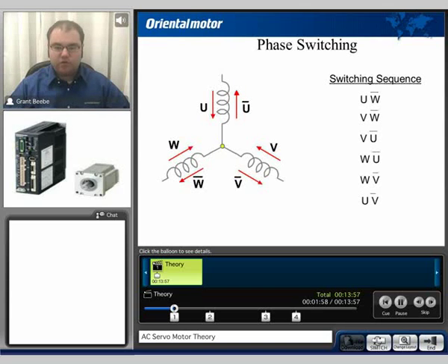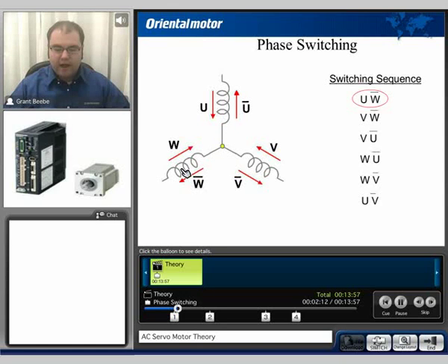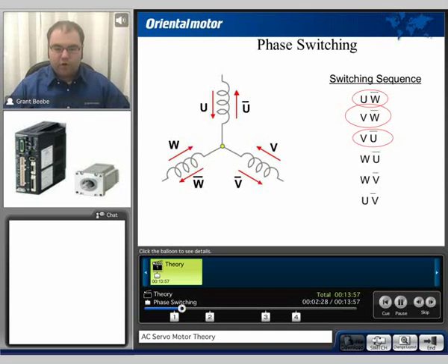The typical switching sequence will be shown here. On the first sequence, the U and the W are activated, so we have current running through U and then exiting out the W. On the next sequence, we have current running through V and then out the W. And on the third sequence, we have current entering through V and then exiting out U. It just repeats that cycle over and over again to generate motion.